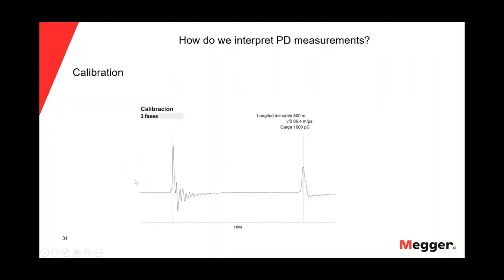It's very important that we have a good calibration. Sometimes I see some reports in which the calibration was not successful. So it is very important that when we analyze a report of partial discharge, we check the calibration.